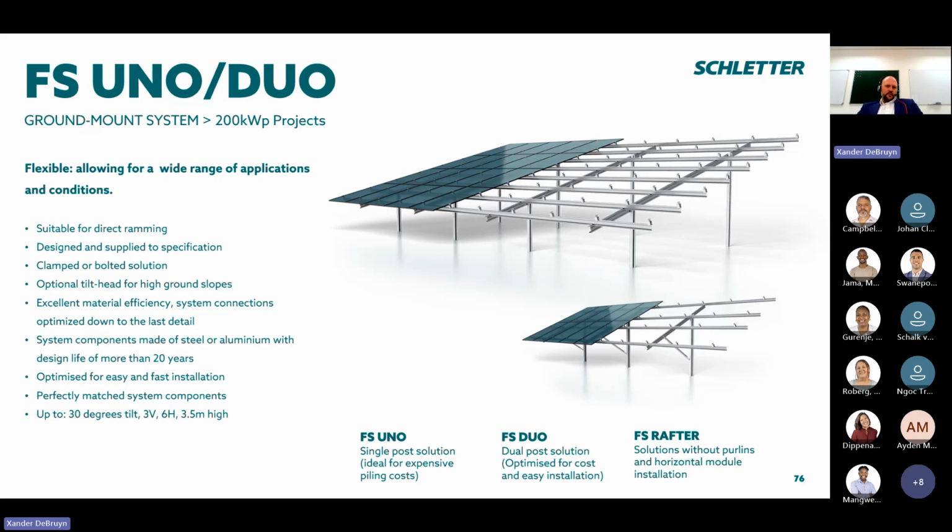If you do have inquiries for ground mount projects bigger than 200 kilowatt peak, where it's possible to do geotechnical investigations, we have the FS Uno and Duo systems, which we've done, I think, over 35 gigawatts worth of these systems globally, where you pile driving posts into the earth. That's a very, very fast process to do with a ramming machine. In some cases, getting up to 200 posts or foundations placed in a day. So I think we had a project in the Cape recently where we did a megawatt in a week in terms of the foundation installation.